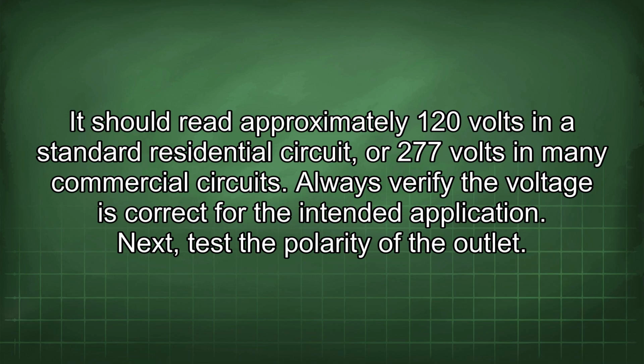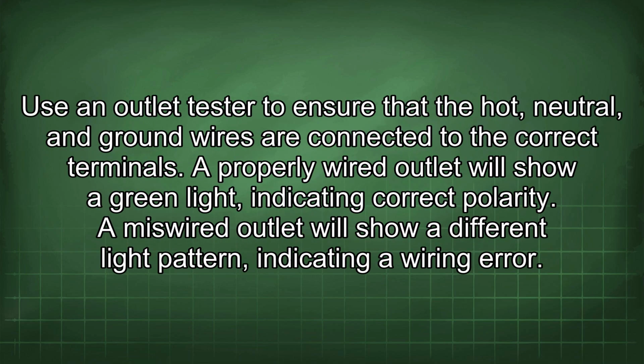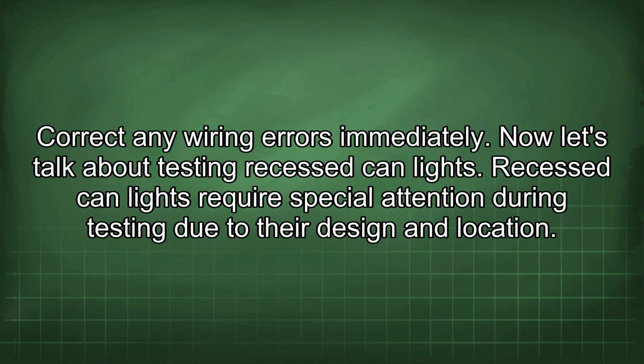Next, test the polarity of the outlet. Use an outlet tester to ensure that the hot, neutral, and ground wires are connected to the correct terminals. A properly wired outlet will show a green light indicating correct polarity. A miswired outlet will show a different light pattern indicating a wiring error. Correct any wiring errors immediately.